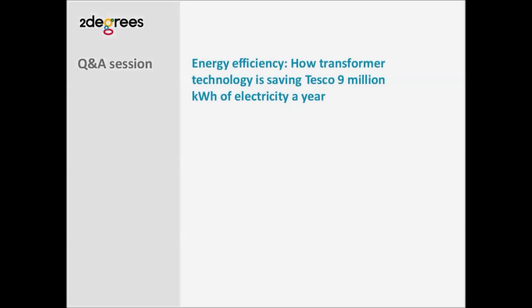Now, it may be required in some instances that small adjustments need to be made to certain equipment on site, but generally this shouldn't be required. It's not about getting the voltage to the lowest possible level. That's not what voltage management is about. It's about finding the right voltage to suit the specific equipment. So usually that won't be required, but in some instances it may mean adjustments to certain controls and relays, and this should be ascertained during the site study.